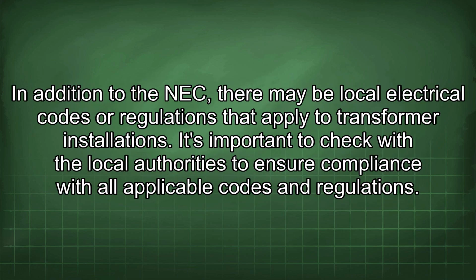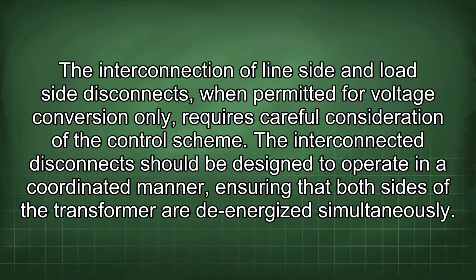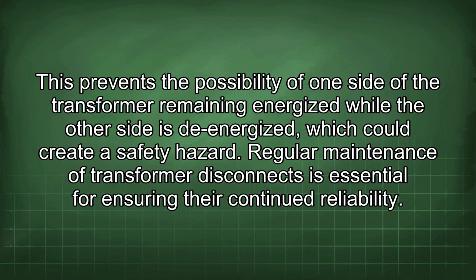In addition to the NEC, there may be local electrical codes or regulations that apply to transformer installations. It's important to check with the local authorities to ensure compliance with all applicable codes and regulations. The interconnection of line-side and load-side disconnects, when permitted for voltage conversion only, requires careful consideration of the control scheme. The interconnected disconnect should be designed to operate in a coordinated manner, ensuring that both sides of the transformer are de-energized simultaneously. This prevents the possibility of one side of the transformer remaining energized while the other side is de-energized, which could create a safety hazard.